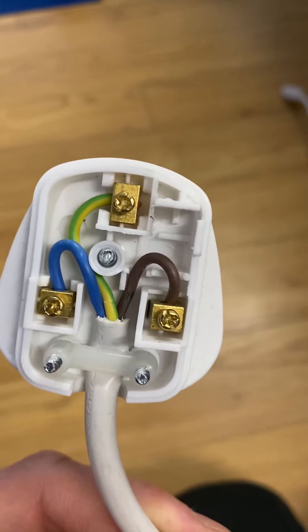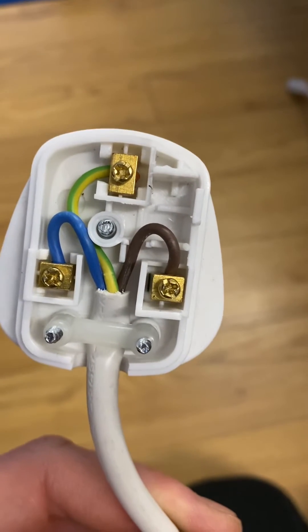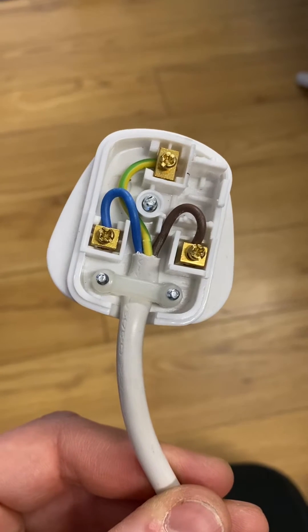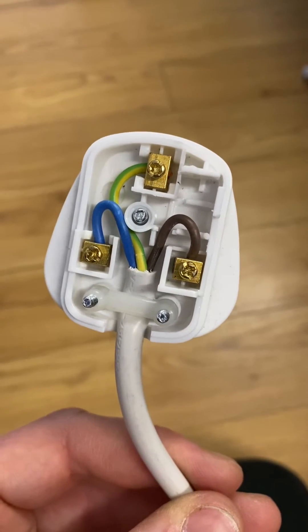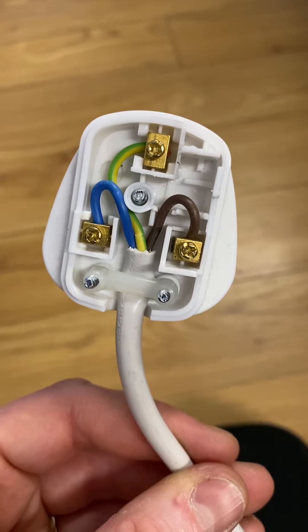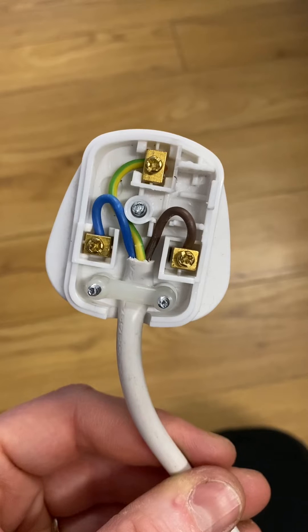You can see here that the fuse holder has been removed and the live cable has been wired straight into the terminal on the back. So the cable is effectively unfused, unprotected. Now that's happened after I PAT tested it properly last year. Someone's obviously been playing around with the plug, or the fuse has gone for some reason, and they've decided just to bypass the fuse holder altogether.